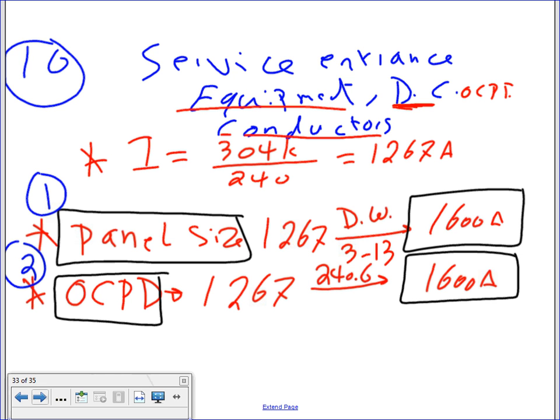This is from 240.6, you get your 1600 amp. In reality, guys, here's what you do. In real life, these will be adjustable circuit breakers. You will tweak them down, most likely, in this case, to 1300 amps, because there are no 1300 amp circuit breakers. They don't make them fixed. They make them adjustable.